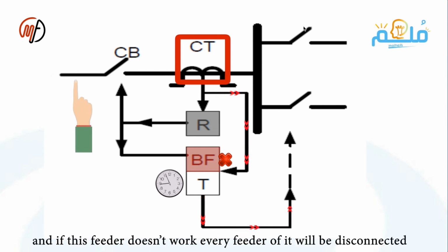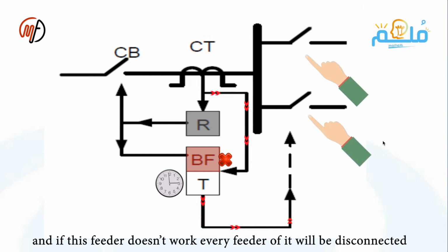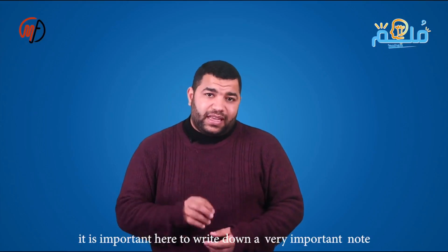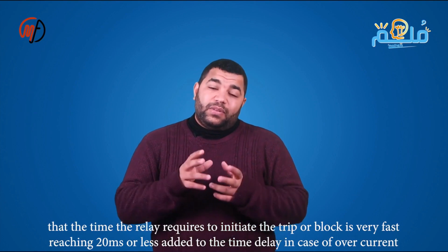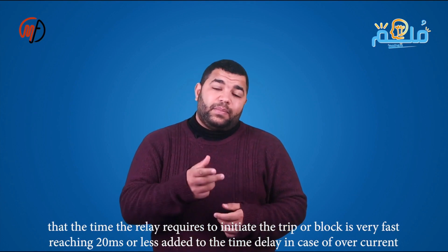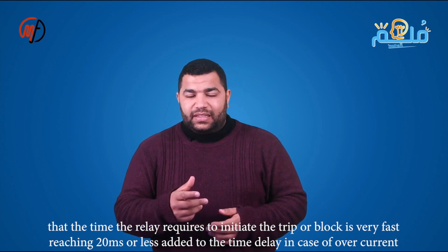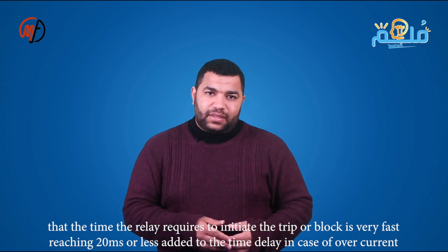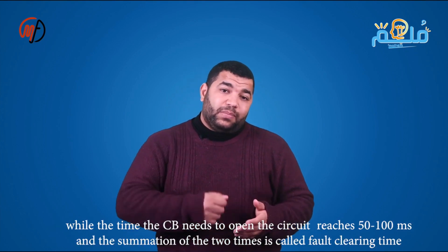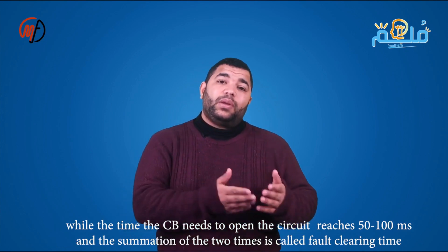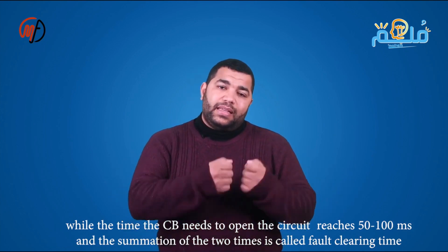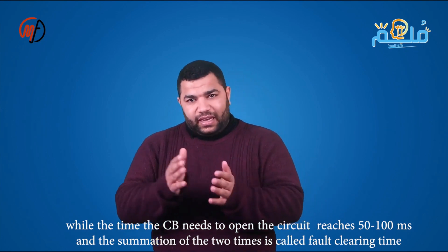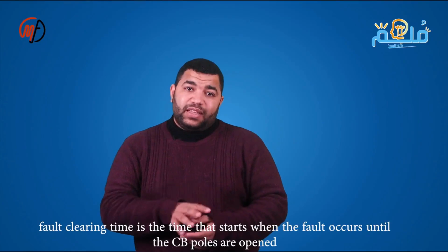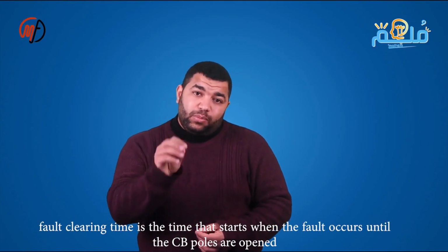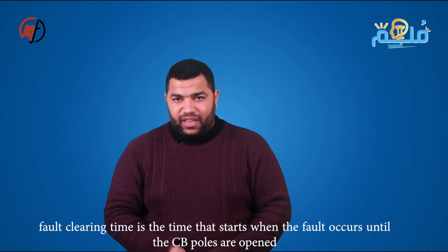All the feeders supplying it will be disconnected, and it's important to note that the time the relay needs to make a decision to trip or block is very quick, reaching 20 milliseconds or less, plus the time delay in case of an overcurrent. Meanwhile, the time the circuit breaker needs to open the circuit ranges from 50 to 100 milliseconds. The total of these two times is called the fault isolation time, which is the fault clearing time. The fault isolation time is the duration that starts from the moment the fault occurs until the circuit breaker opens.